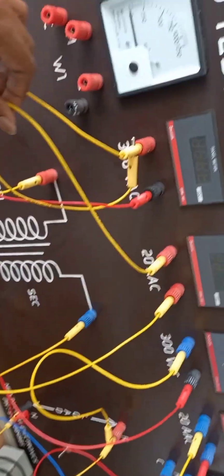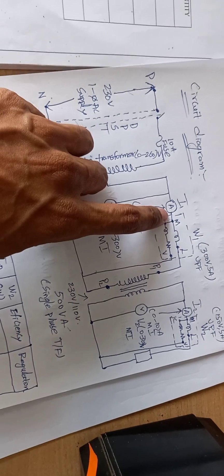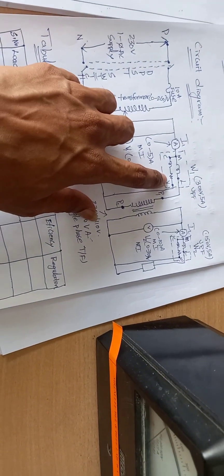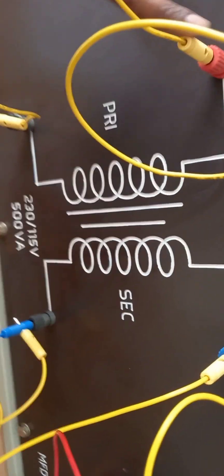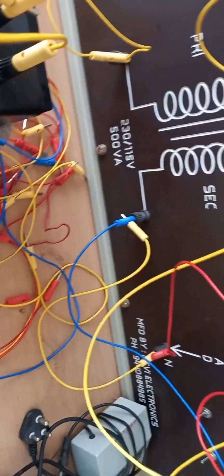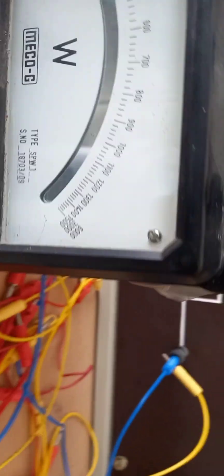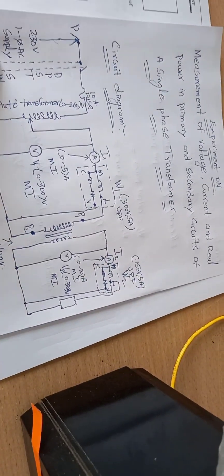You can observe that I have already connected the entire circuit as per the circuit diagram. The first two terminals of the auto transformer are connected to the voltmeter, and from the same first terminal of the voltmeter it is connected to the first terminal of the ammeter. The ammeter's second terminal is connected to terminal M of the watt meter. Also, terminal V of the watt meter is directly connected to the secondary terminal of the primary winding — I have taken 300 volts for that V terminal. So the primary side connections are completed.